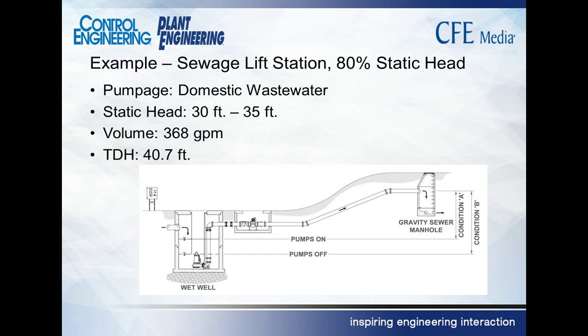Here's a system typical of a lift situation, a high elevation system, high static head. It's a sewage lift station. If you look, the static head is between 30 and 35 feet, and the total dynamic head is 40 feet. So you've only got 5 or 10 feet of friction head, depending on the level in the sump, compared to 30 feet of head elevate.